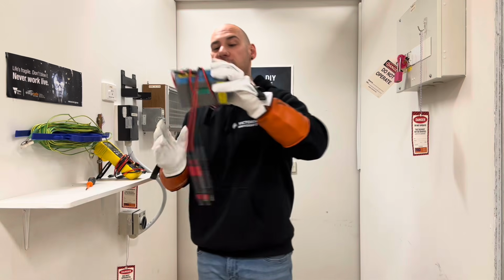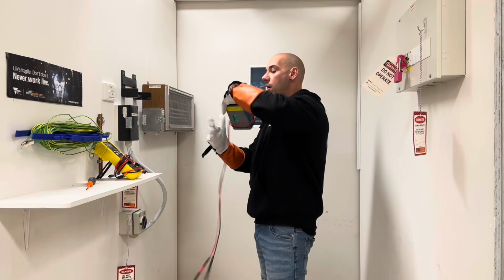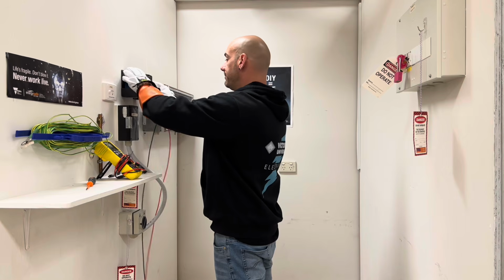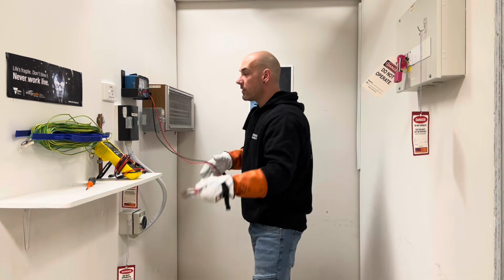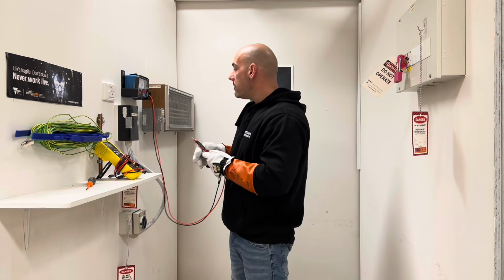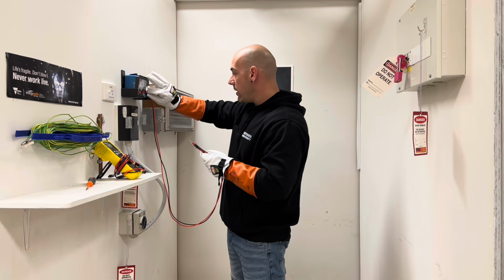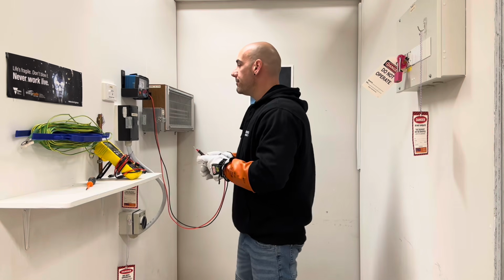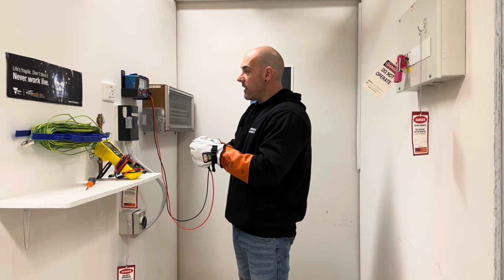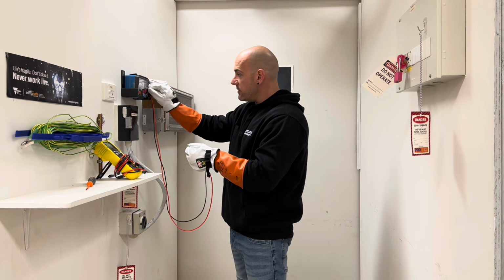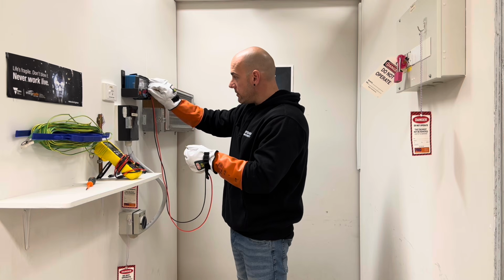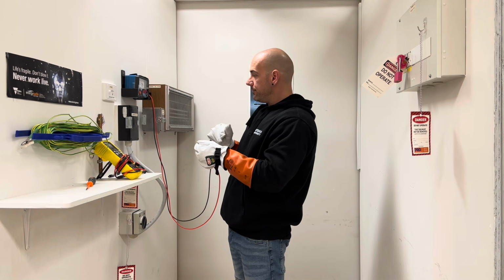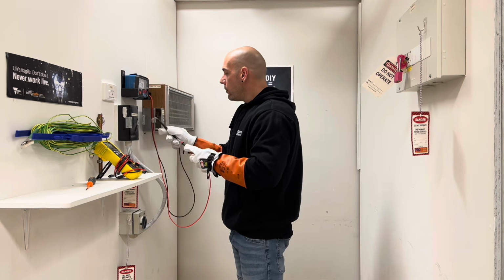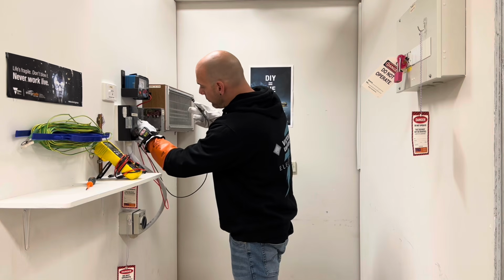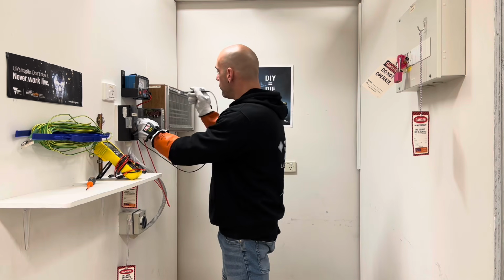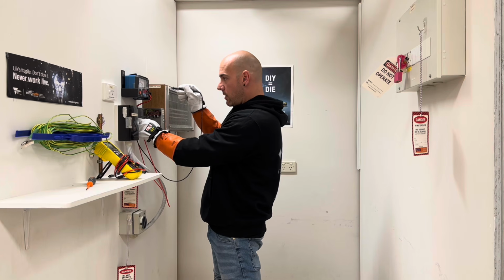First thing we will be doing is grabbing our analog IR and continuity tester. Checking the battery, it's good, yep. And setting it to the 3 ohm scale. We short our leads out and we zero the meter to read 0 ohms. Okay. We're going to do a continuity test from the earth terminal to the frame of the appliance.